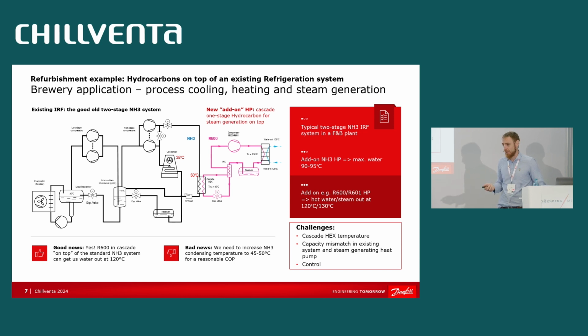People are not having a problem to smoke cigarettes next to their barbecue, but they get very nervous if there is a closed circuit of hydrocarbon in a refrigeration system. So we need to play it smart. And from technical perspective, with hydrocarbons, you can go to these higher temperatures. Also with low GWP refrigerants, you can also go to these high temperatures of condensation. There are some discussions on political level about the future of low GWP refrigerants. I don't know. We are engineers. We look into what is technically possible and what is the best solution.